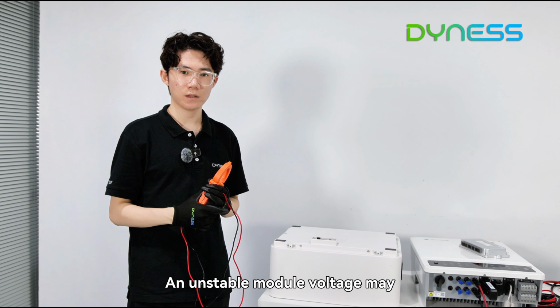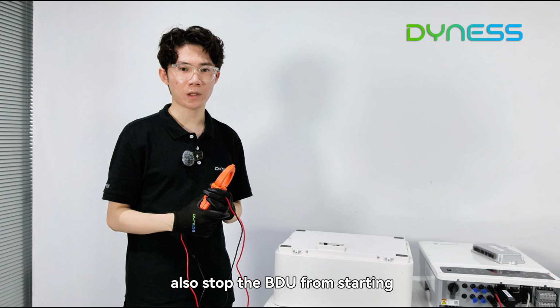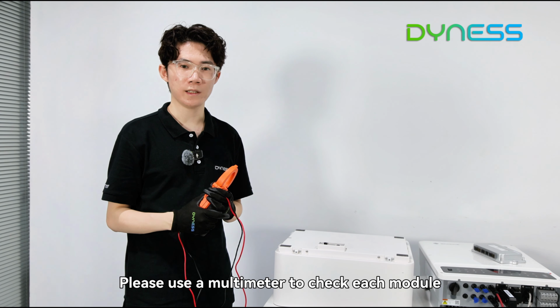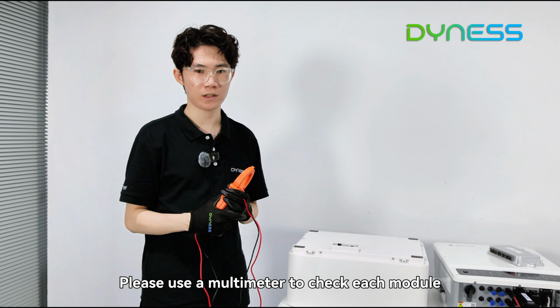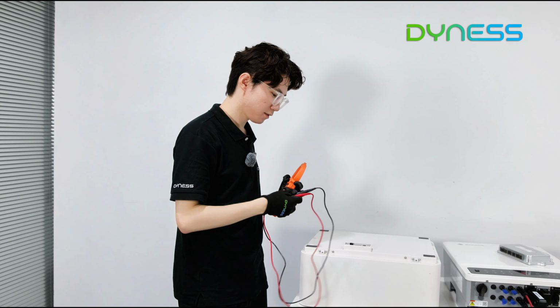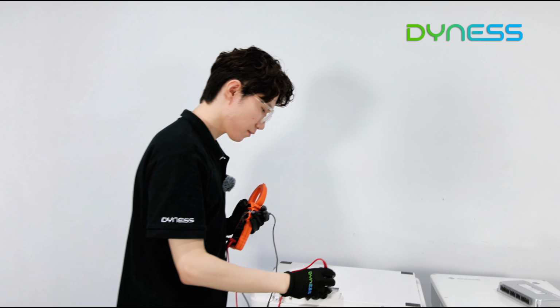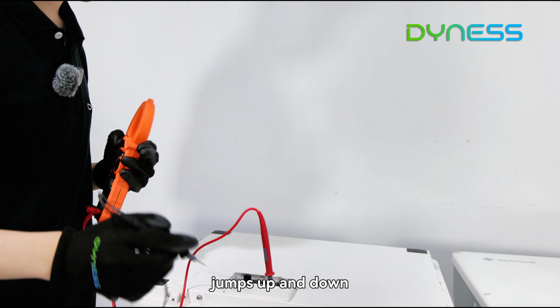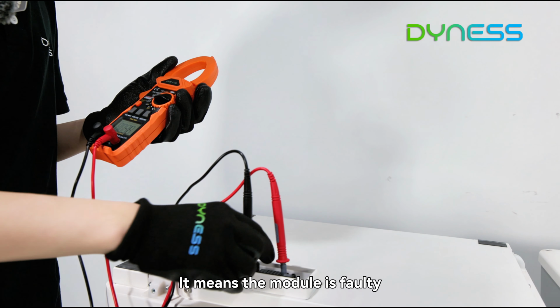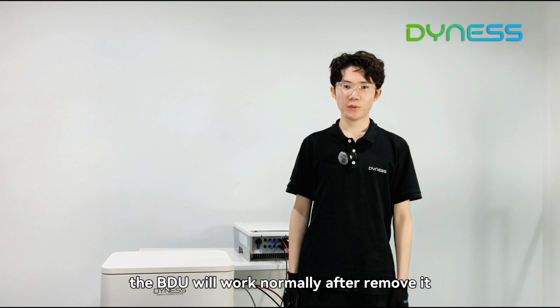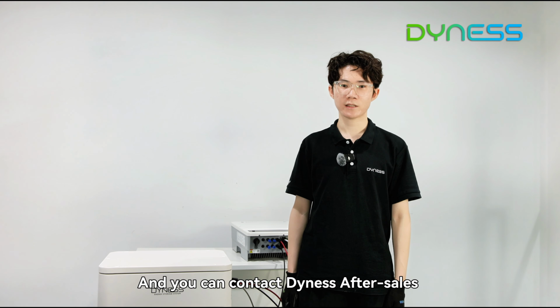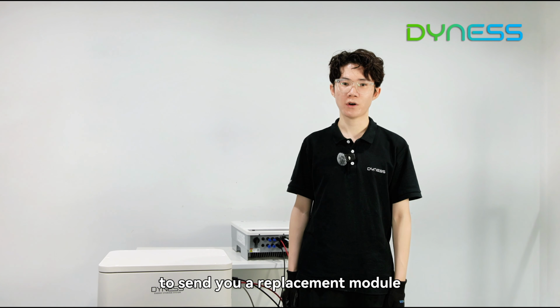An unstable module voltage may also stop the BDU from starting. Please use a multimeter to check each module. If the voltage jumps up and down, it means the module is faulty. The BDU will work normally after you remove it, and you can contact Dyness after-sales to send you a replacement module.